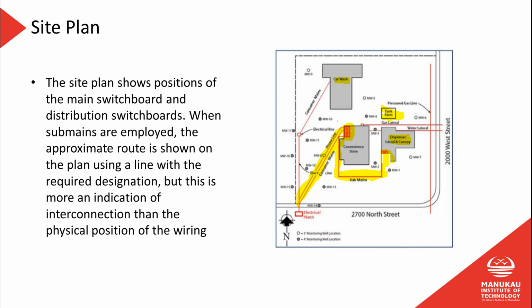So as an aside, I can remember an example where I had a drawing like this. It was an as-built. It showed from one end of the service station to the other a duct that was running, and I needed to get a cable through there. So I found each end of the duct, an underground duct, a 4-inch pipe. It was about 50, maybe longer, meters that I needed to run this cable, and I spent about 2 days trying to get a cable through this thing, and I just could not, from either end, not with every method I tried, nothing. Eventually we gave up, and I decided we would just dig it up.